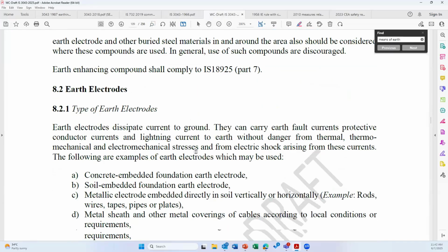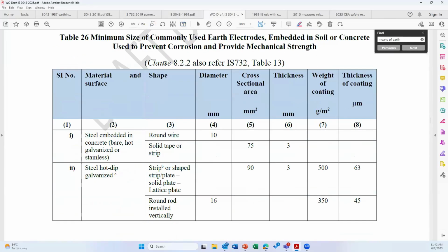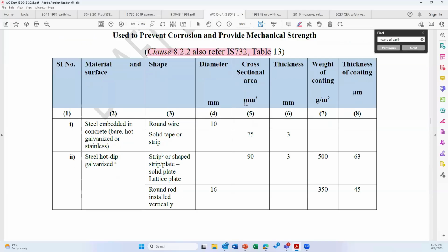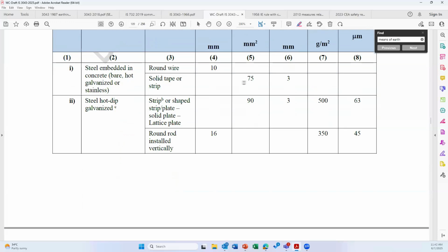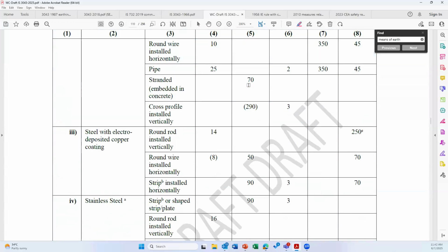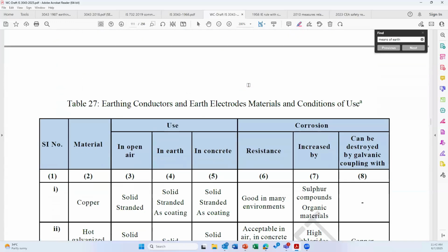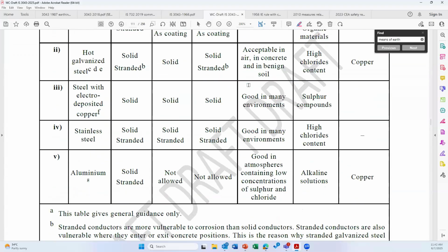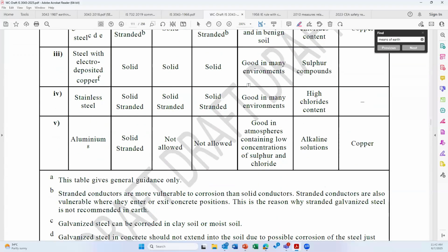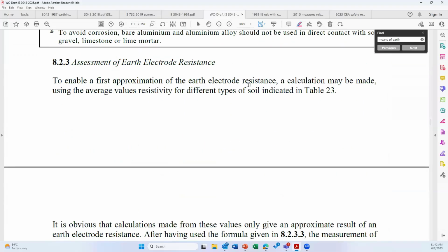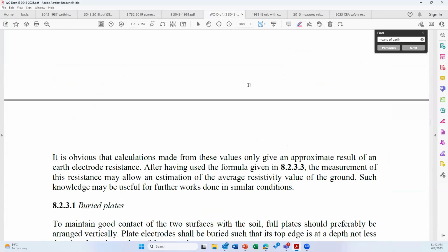Earth electrodes. The table, minimum size of earth electrode, has been taken from IS 732 as well as last year's NEC. Basically, the information is from IEC 60364 and IEC 61936. All over the world, all the international standards are following this table as the minimum size of earth electrode, with the conditions of installation. If you have copper and if you have GI, what kind of problems can come. All this information is being included.